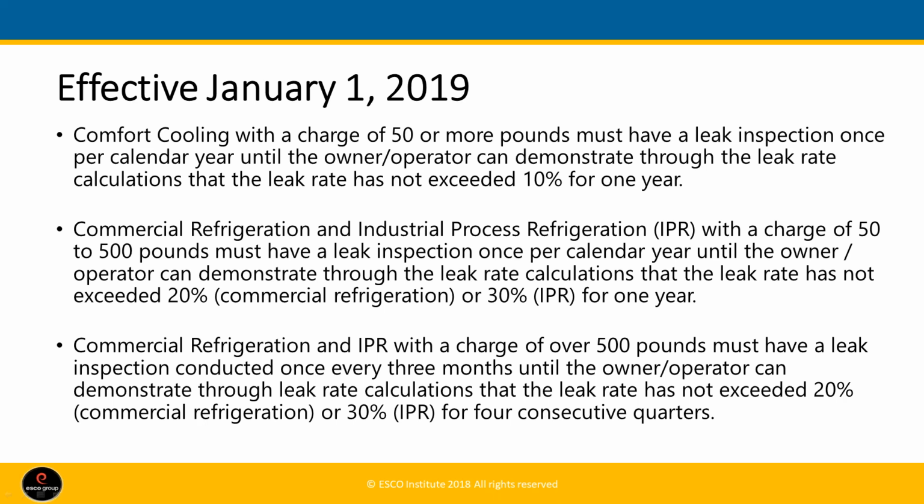in that calendar year. For commercial refrigeration and industrial process for charges of 50 to 500 pounds, they must also have a leak inspection once per calendar year until it's demonstrated that the leak rate calculations have not exceeded 20% for the commercial and 30% for industrial process for 1 year.